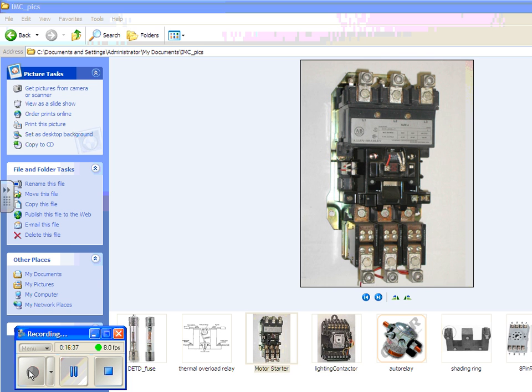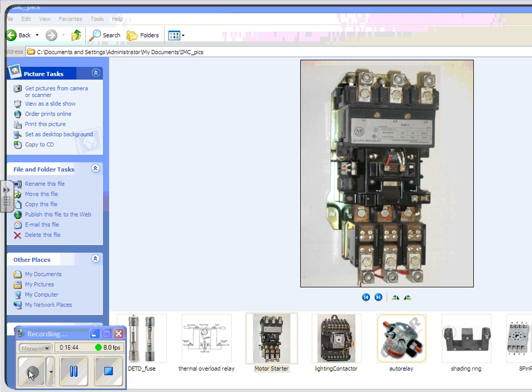All right, now we have our standard motor starter, and you can see here at the top that we have the coil, and it can be any voltage. You can have a coil for whatever voltage you're using to control the circuit with, and these are completely separate from the power contacts. The power contacts come in here, here, and here, and leave here, here, and here. And you notice that we have an overload block down here, an overload relay. In there is going to be a normally closed overload contact that breaks the control circuit. And over here on the left, you can probably see where we have the wires for the holding contact, and they should be marked 2 and 3.